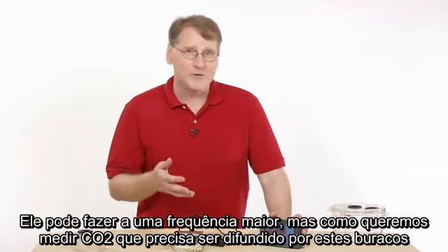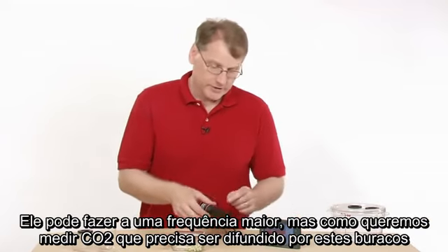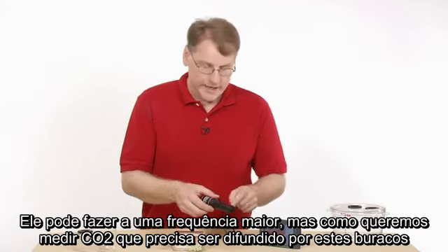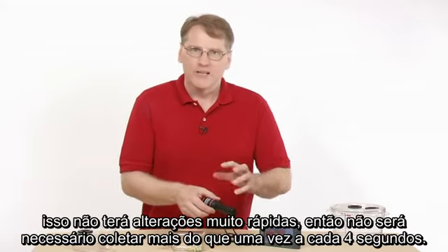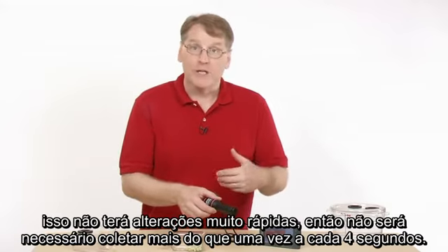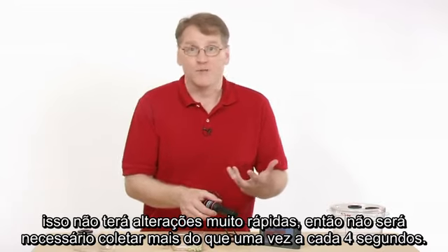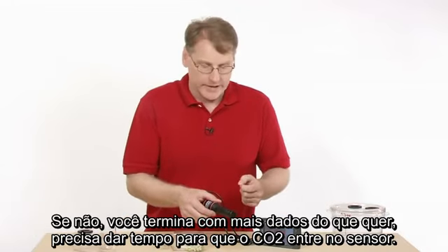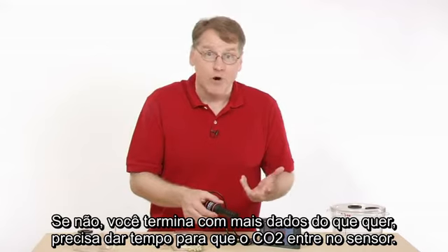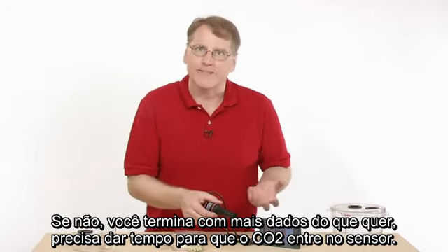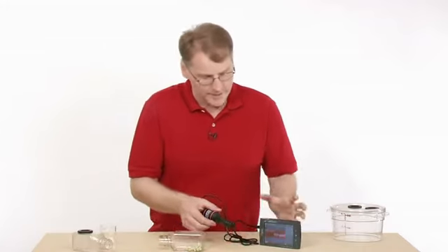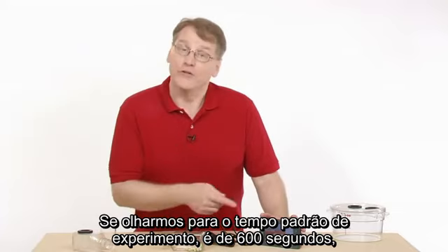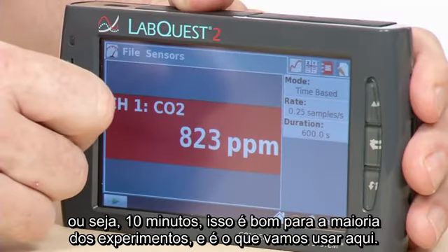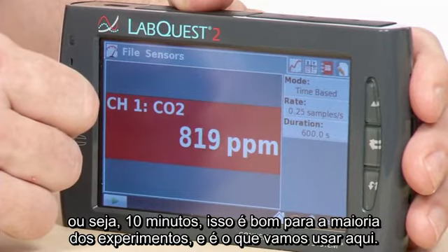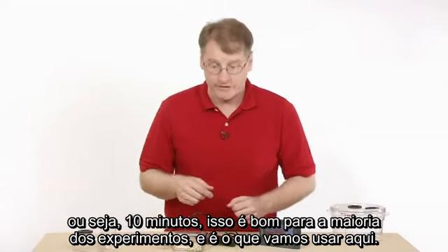It can go faster than that, but because we're measuring the CO2 that has to diffuse through these holes, it may not change all that rapidly. So collecting data faster than, say, 4 points per second, you really don't have to do that. And you end up generating maybe more data than you want. So you need to allow time for that CO2 to make it into the sensor there. And then if we look at our default time for this, it actually is 600 seconds, so it's a 10-minute. And that's fine for a lot of experiments. And in fact, for this one, we'll just use that as our default setting here.